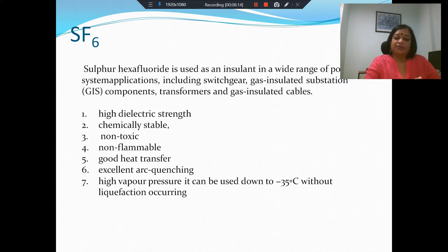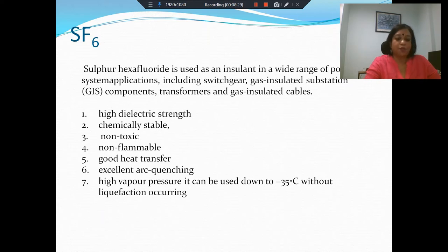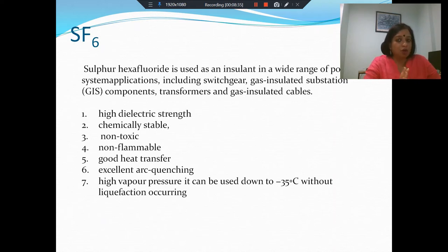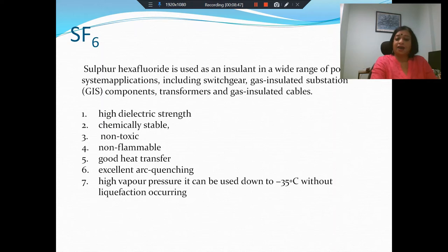What is the reason SF6 is the insulating medium of choice in very many situations? Primarily because it has very high dielectric strength — several times more than that of air, about three times more. It is chemically stable, so it does not decompose very easily. It is non-toxic and non-flammable.